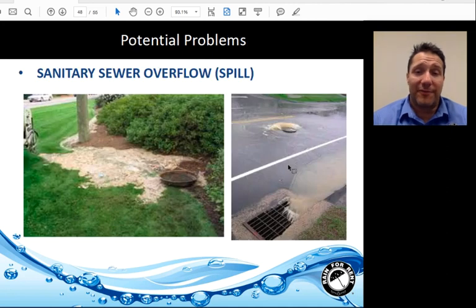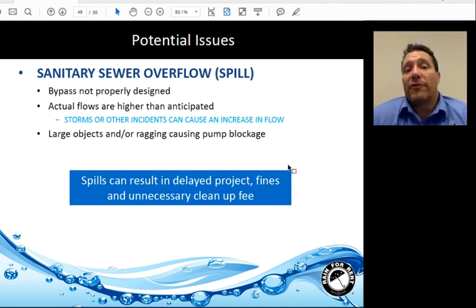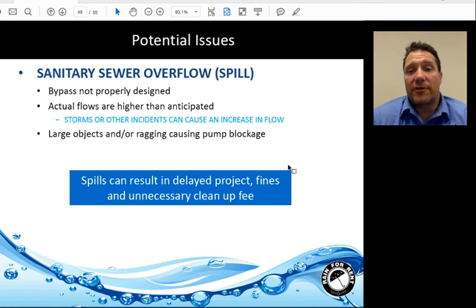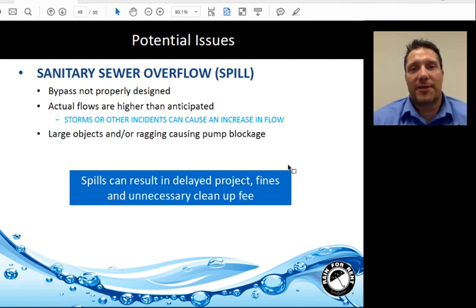Complete system failure leads to sewage spills or sanitary sewer overflows (SSOs). An SSO can be caused by a bypass that is not properly designed or maintained, actual flows higher than anticipated, storms or other incidents causing increased flow, or large objects and ragging causing pump blockage. Spills can result in delayed projects, fines, and unnecessary cleanup fees.